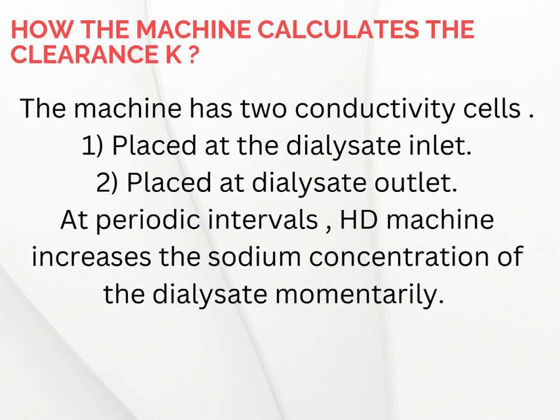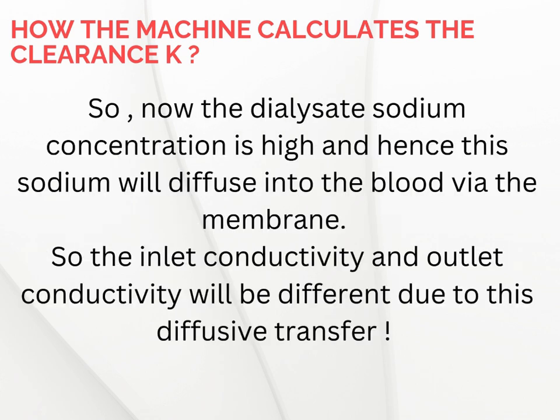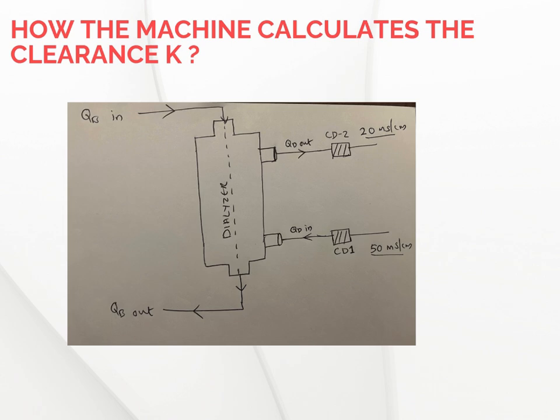This clever trick lets the machine estimate urea clearance in real time. For example, if the inlet conductivity cell measures sodium as 50 and the outlet conductivity cell measures sodium as 20 — you can see this in the picture — approximately 30 units of sodium must have diffused from the dialysate to the blood. Since sodium and urea have the same diffusive properties, 30 units of urea must have diffused from blood to dialysate. You just estimated the urea clearance rate — it's relatively very simple.